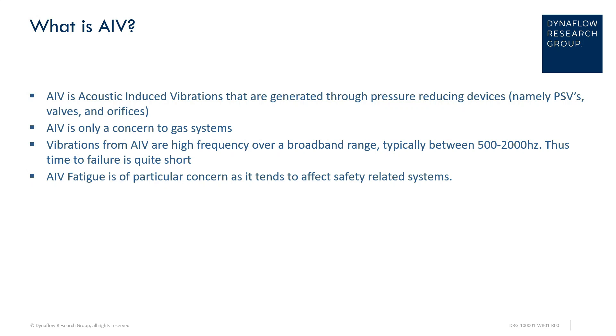AIV stands for acoustically induced vibrations. These vibrations are generated by gaseous flow passing through a pressure-reducing device such as PSVs, valves, and orifices. AIV induces a high-frequency broadband excitation that is typically over a range between 500 to 2000–2500 hertz.